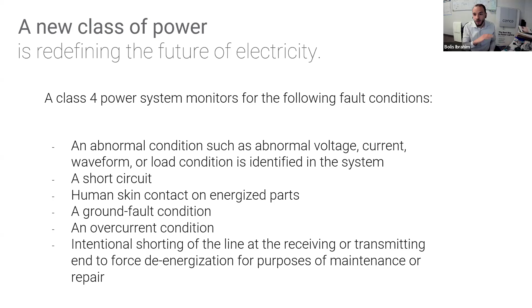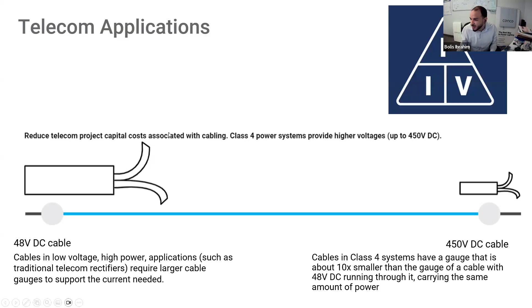The UL certifications: UL 1400-1, that's the outline of investigation. So it's not yet a standard, it hasn't been turned into a standard. The outline of investigation for fault managed power is -1, and the outline of investigation for fault managed power cables is -2. This is what UL is doing right now. We're also on the technical subcommittee for CSA, bringing this to the Canadian Standards Association as well. And the IEC will follow suit. Hopefully we have a unified standard across North America at some point. This is cool for telecom because you're taking 48 volt cables. If you've ever seen a telecom 48 volt cable, actually, I have one. I have a picture, I think. This guy right here, 48 volt telecom cable.